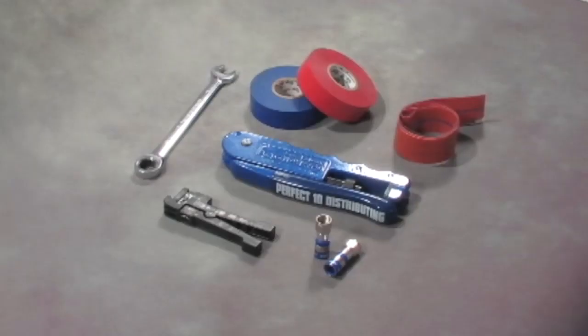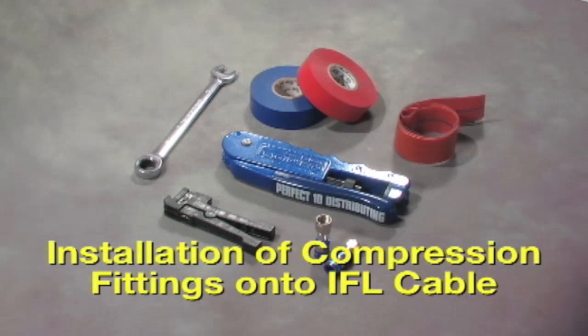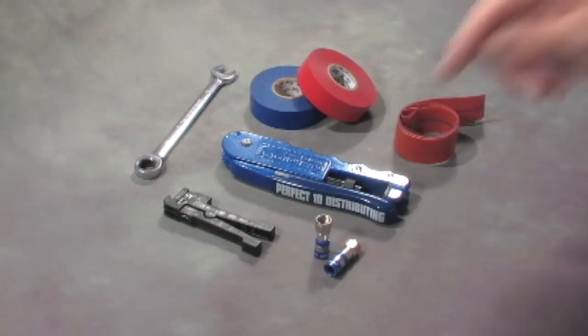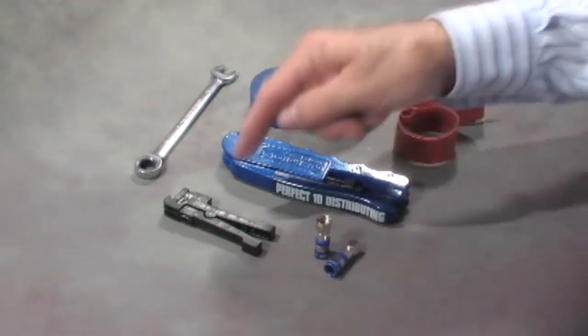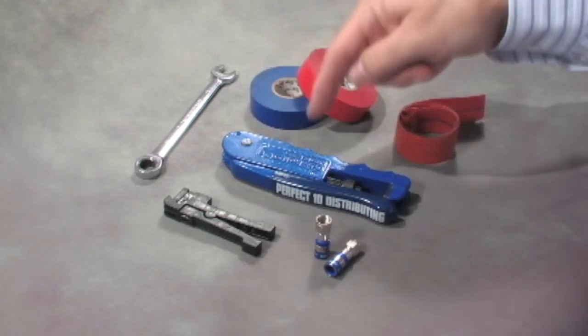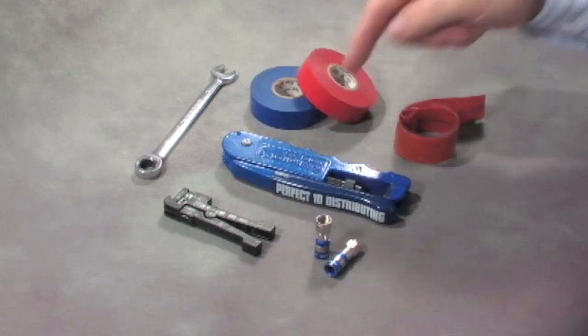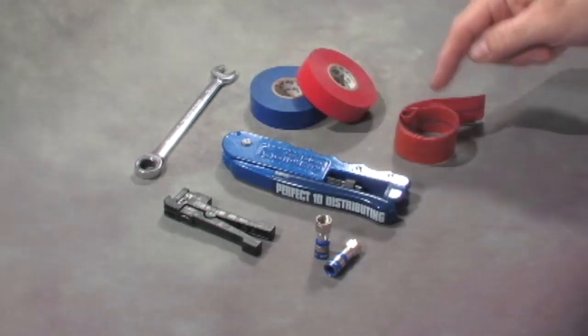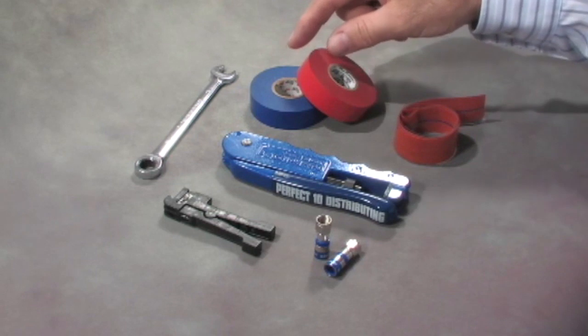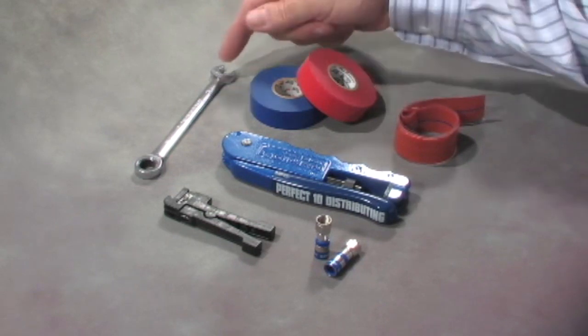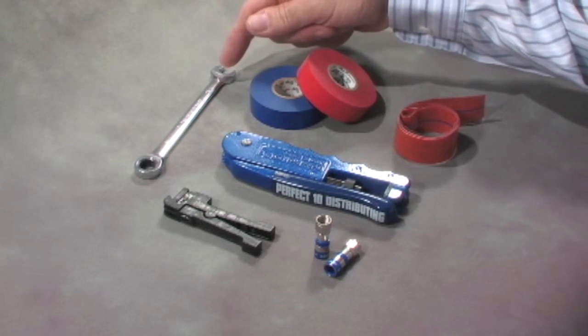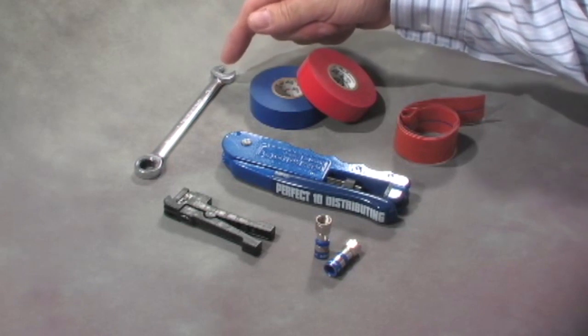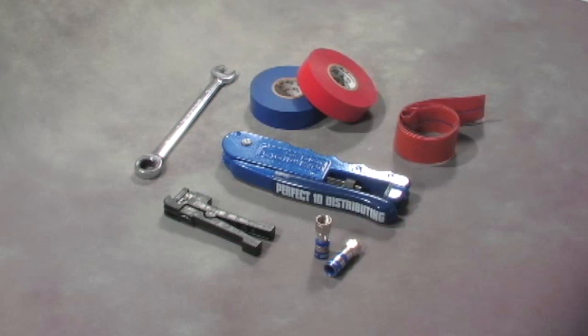We are here today to demonstrate the installation of compression fittings onto an IFL cable. We have our connectors, wire stripper, compression tool, weatherproof tape, phase tape used to mark the IFL cable for transmit and receive, and a 7/16 wrench used to tighten the connections, whether it be on the outdoor unit or the indoor unit.